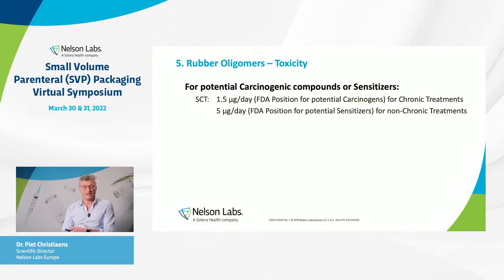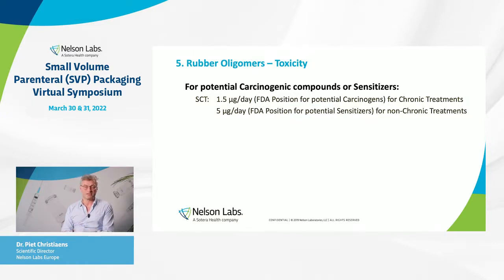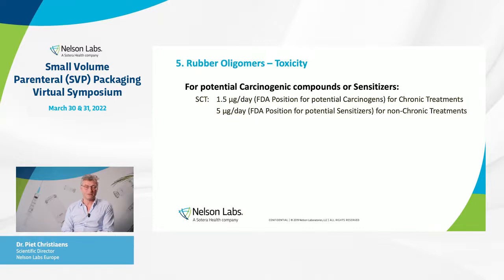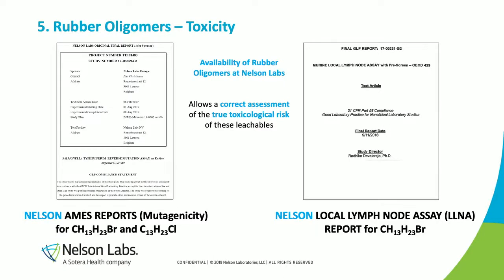In terms of qualification of those compounds, the FDA looks at a safety concern threshold (SCT) for chronic treatments at 1.5 micrograms per day and for non-chronic treatments at 5 micrograms per day, related to the potential sensitization potential. Because we have all those oligomers available at Nelson Labs, we performed a further evaluation: AMES testing on the C13-brominated and C13-chlorinated oligomers, as well as a local lymph node assay on the C13-brominated to detect any potential sensitization issues. This allows a correct assessment of the true toxicological risk for those leachables.